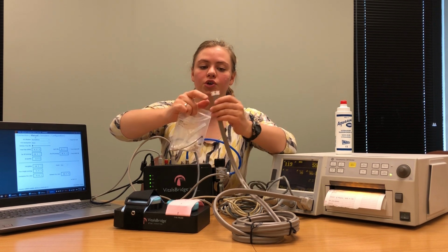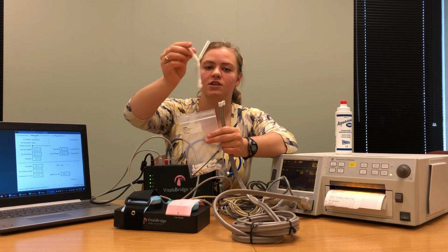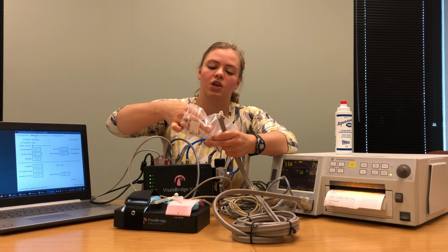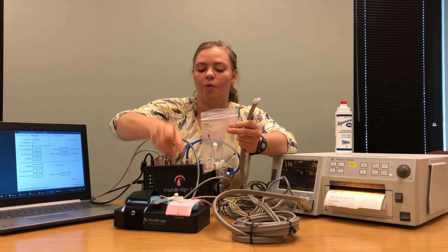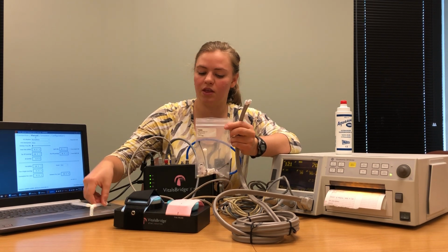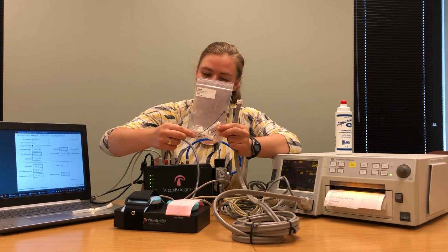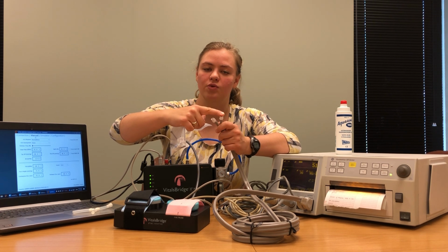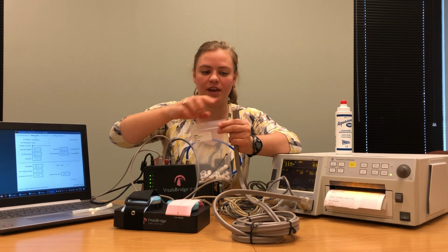If you have a 2-tube non-invasive blood pressure cable, you're going to need this Y adapter. If you have a 1-tube, you're going to need this single tube adapter. Once you've pulled out the adapter that matches your non-invasive blood pressure cable, go through each of the fittings included with your non-invasive blood pressure fitting kit and find two that will clip perfectly onto the ends of your non-invasive blood pressure cable.